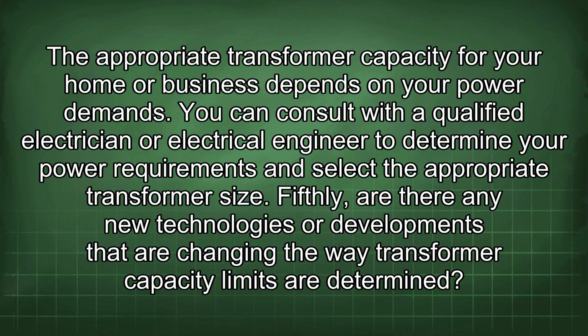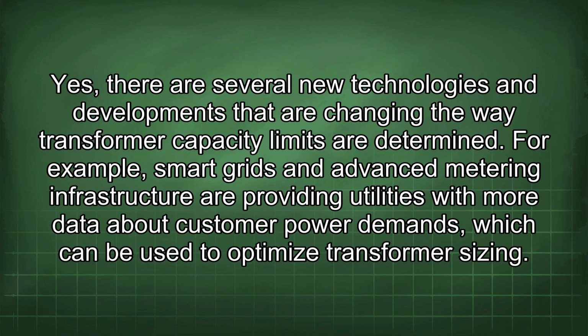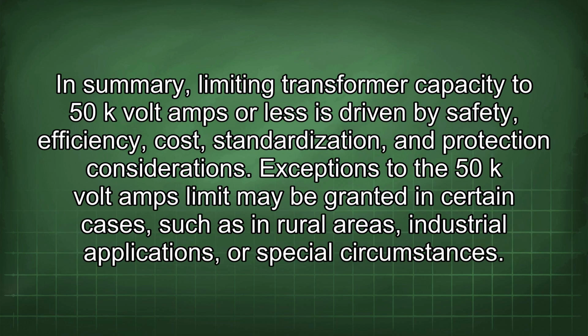size. Fifthly, are there any new technologies or developments that are changing the way transformer capacity limits are determined? Yes, there are several new technologies and developments that are changing the way transformer capacity limits are determined. For example, smart grids and advanced metering infrastructure are providing utilities with more data about customer power demands, which can be used to optimize transformer sizing. In summary, limiting transformer capacity to 50 kVA or less is driven by safety, efficiency, cost, standardization, and protection considerations.